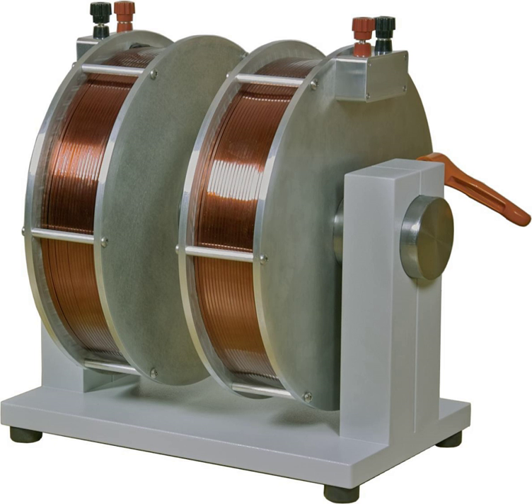However, the limit to increasing N or lowering the resistance is that the windings take up more room between the magnet's core pieces. If the area available for the windings is filled up, more turns require going to a smaller diameter of wire, which has higher resistance, which cancels the advantage of using more turns. So in large magnets there is a minimum amount of heat loss that can't be reduced. This increases with the square of the magnetic flux, B².